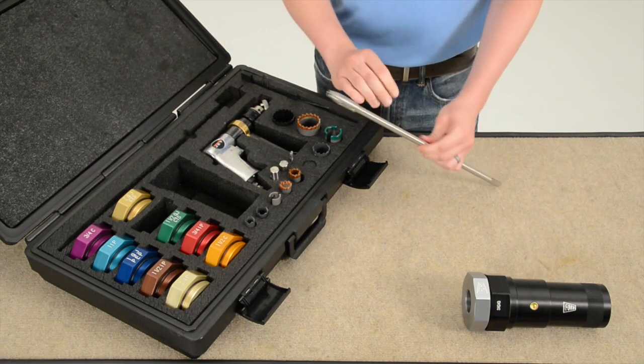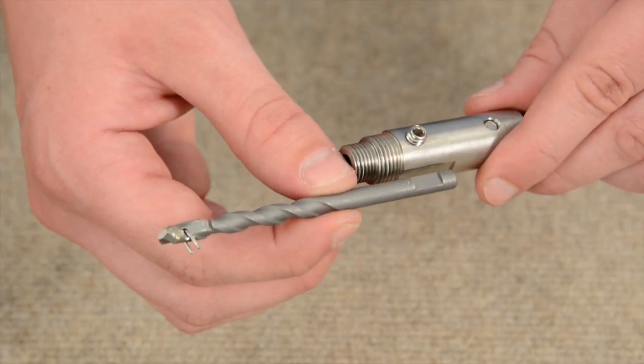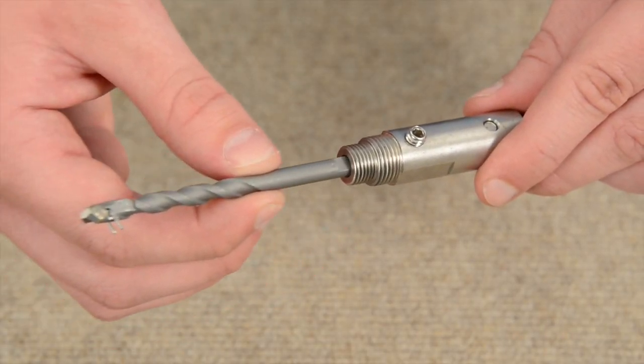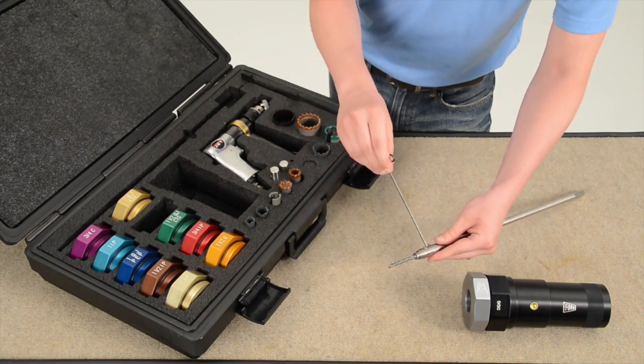Insert the coupon retaining pilot bit onto the stainless steel shaft and line up the drill bit flat with the set screw. After inserting, tighten the set screw with the hex wrench to secure the bit.